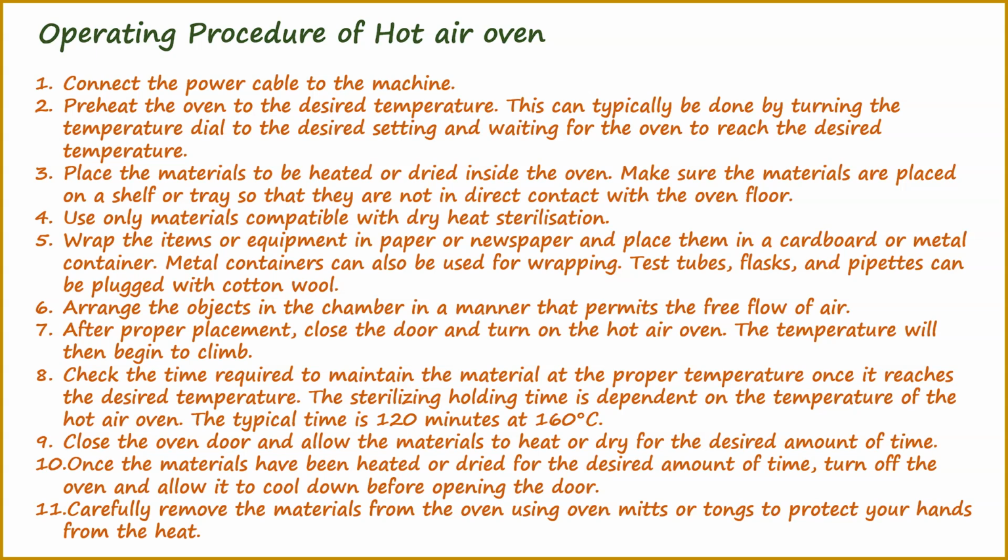After proper placement, close the door and turn on the hot air oven. The temperature will then begin to climb. Check the time required to maintain the material at the proper temperature once it reaches the desired temperature. The sterilizing holding time is dependent on the temperature of the hot air oven. The typical time is 120 minutes at 160 degrees Celsius.